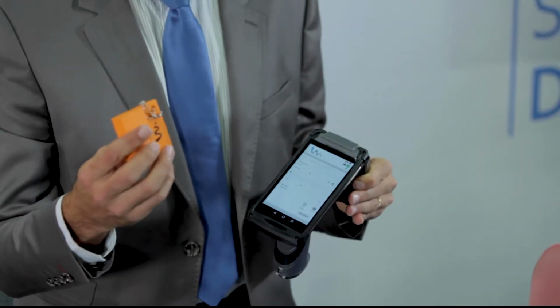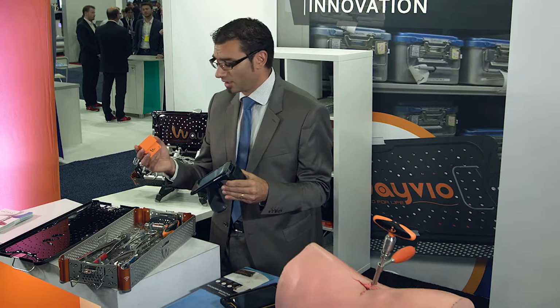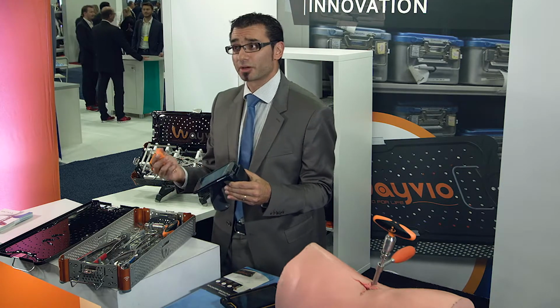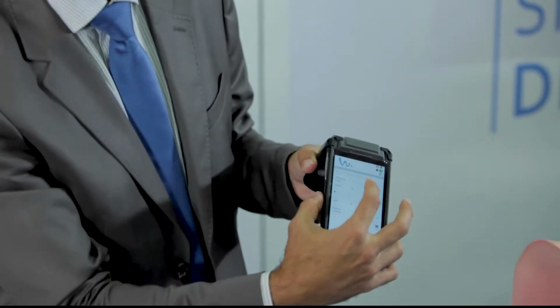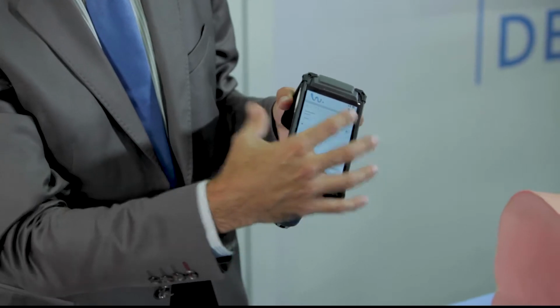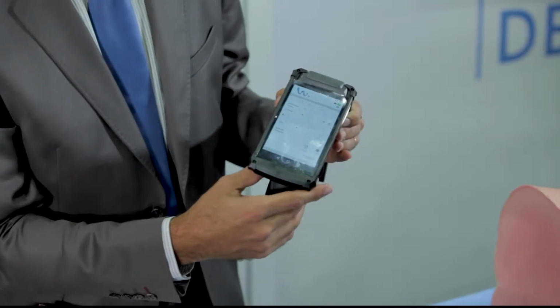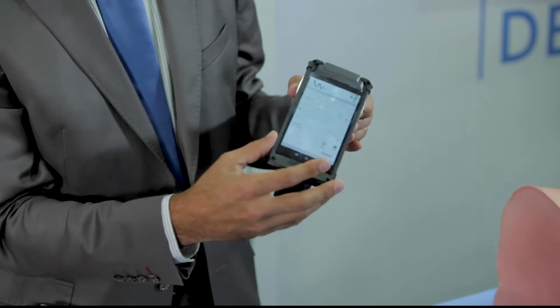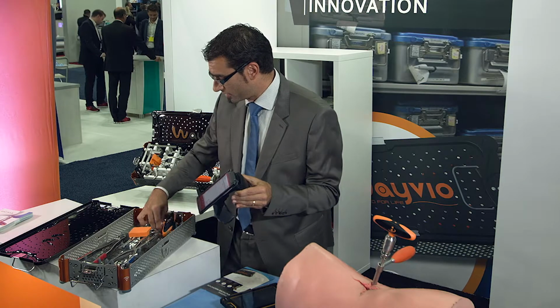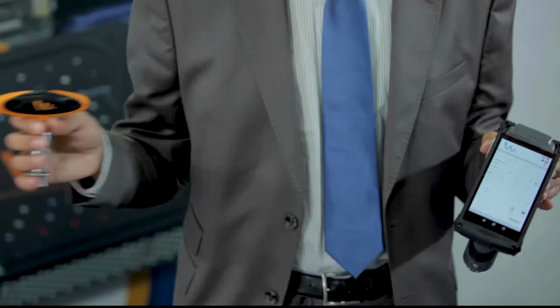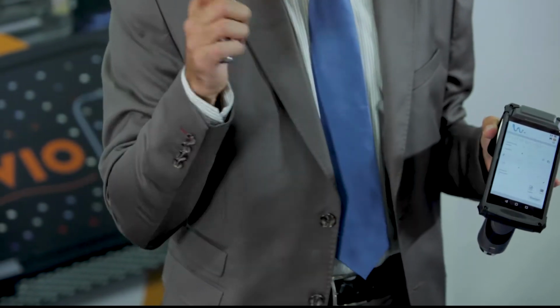That's the Wayvio module for the tray. This module contains a thermal sensor and a microcontroller in order to count the number of sterilizations that the whole tray went through. So that's what you have when you scan the tray. It will tell you the last sterilization date. It will also tell you if one instrument inside fell. This torque limiter is equipped with an acceleration sensor. So anytime the instrument falls on the ground, it will detect it, record it in this memory, and when you scan the whole tray, it will give you a warning on that.